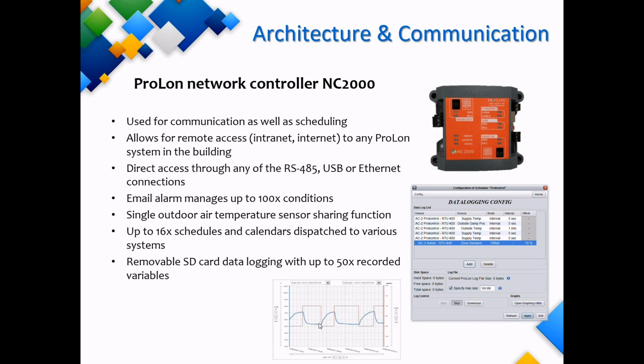There is also an outdoor air temperature sharing function, in that a single outside air temperature reading can be shared across the network to all devices. So you can use a single outside air temperature sensor for all your networked devices.